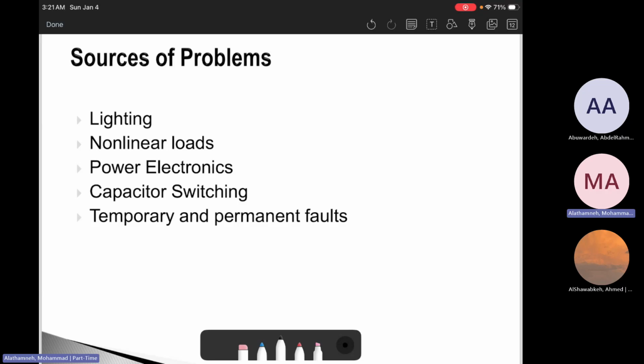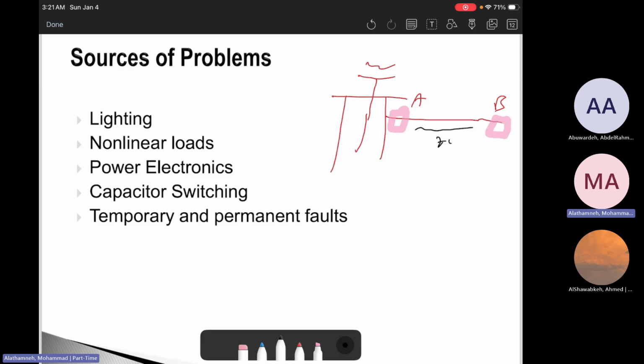So keep in mind, again, in Jordan, here is the substation, and then we have multiple feeders. Then in this feeder, we have sub feeders. Then you can say the customer at the end of the feeder and the customer at the beginning of the feeder. Here is customer A, customer B. Customer B will face many power quality problems while customer A can barely notice small power quality problems. Again, the reason is that the impedance here will be higher, the voltage regulation will be weaker, and recovery gets slower.